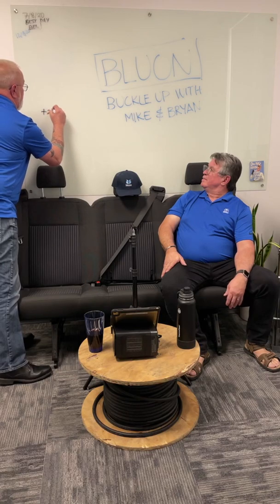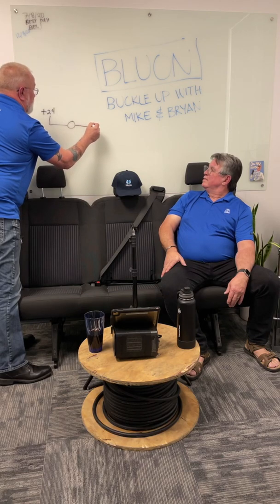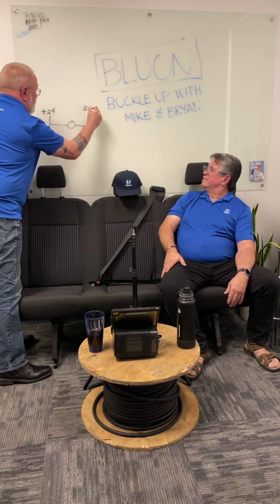Someone's asking, what is the purpose of the common wire? Well, you've got to complete a circuit. If you want to call one side the hot wire and the other side the common wire, it's just the other side - it completes a circuit. You have to have the plus 24 coming into the coil. If this doesn't go back to 24 common, you don't complete the circuit. Now if you apply 24, the coil will energize. Right now that coil is not energized. So this could be a pressure switch or anything like that.